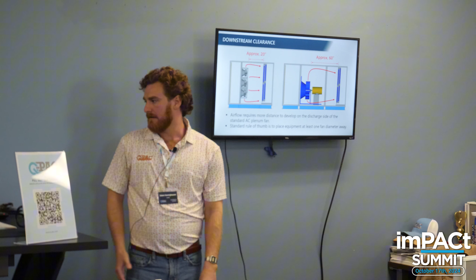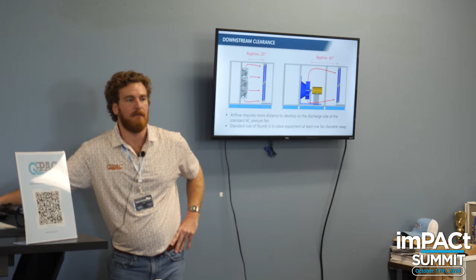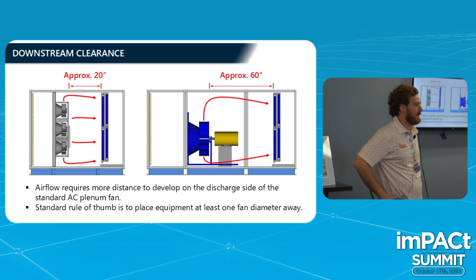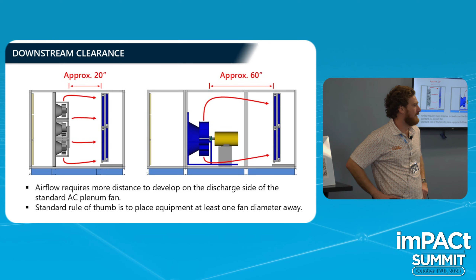For downstream, it requires more distance to develop on the discharge side for the AC plenum fan. I don't think it's that big of a deal, but the rule of thumb is to go at least one fan diameter away from the coil. I'd stick to that. If you're sizing a unit and worried about it, give us a call or your account manager a call and we can go over it with you. But in general, you want one fan diameter away for your coils and outlets.